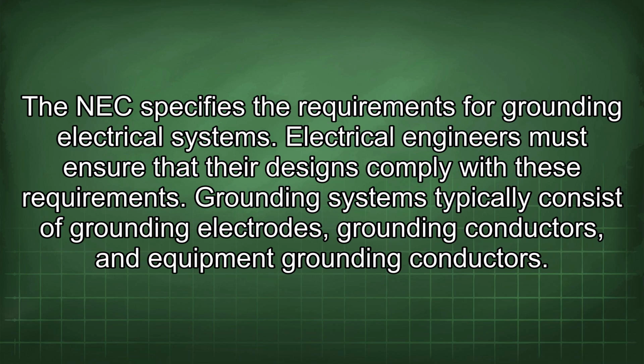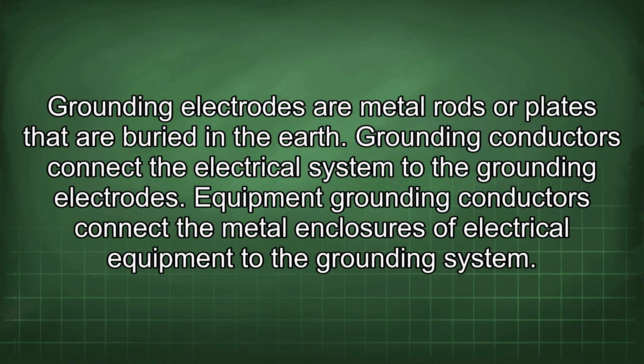Grounding systems typically consist of grounding electrodes, grounding conductors, and equipment grounding conductors. Grounding electrodes are metal rods or plates that are buried in the earth. Grounding conductors connect the electrical system to the grounding electrodes. Equipment grounding conductors connect the metal enclosures of electrical equipment to the grounding system.